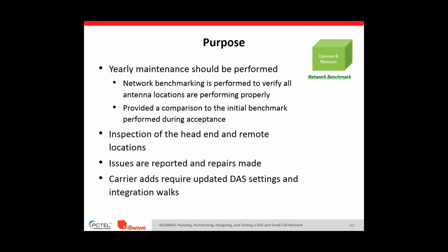You should always inspect the head end and the remote locations, making sure that all connections are still torqued properly, that there are no kinks in coaxes, that everything is performing properly, and that there are no alarms on the system. Any issues should be reported and repairs should be made. Anytime you do a carrier add, adding an additional carrier or technology to that DAS network, it's very important that you bring in commissioning people that are certified and understand how to commission that additional carrier on the DAS. If you don't, that could impact the other carriers that are on the DAS. Every carrier is allotted so much power and percentage of power on a DAS network. You want to make sure that you're not stealing from one carrier and reducing their coverage footprint by adding another technology or carrier for another wireless service provider.